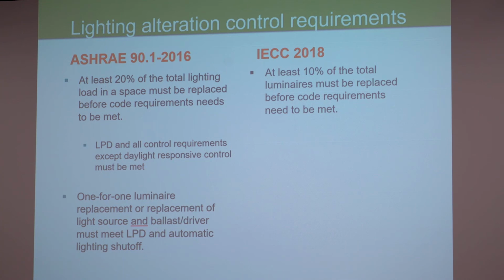Okay, so we've been talking about the new construction requirements. These are the requirements for existing building alterations as far as lighting. For 90.1 2016, if you replace more than 20% of the lighting load in a space, you have to comply with all the new construction requirements except for daylight responsive controls. Okay?